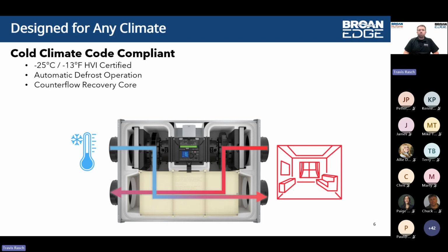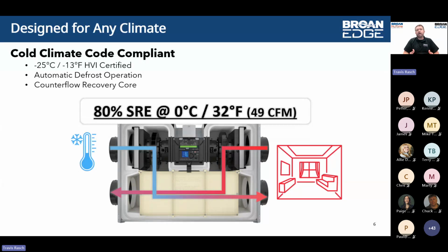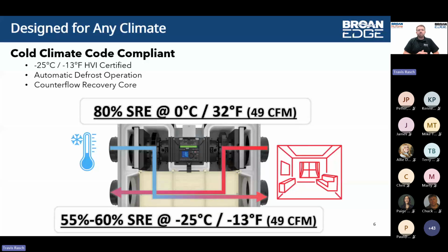And so you're going to see we're able to achieve, even in this very compact platform, high sensible recovery efficiency, as well as the necessary SRE, whether it's 55% or 60%, depending on where you're at, which is required at those cold temperatures. Again, these are already HVI certified. You'll be able to get access to this data, whether it's on the directory or on the spec sheets. Do know that this new platform was truly designed for the complete North American market, whether you're in the extreme hot climates or in those extreme cold climates, like the values you see here.